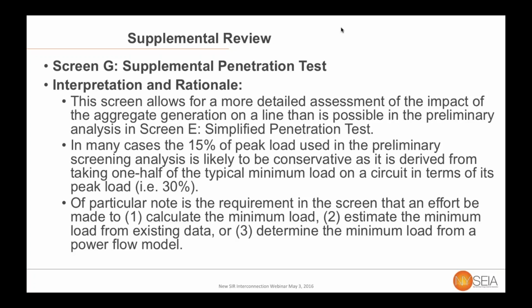It's also important to note that the screen does not require the data to exist for your particular line, but asks, can it be calculated, estimated, or determined from a power flow model? And so if the minimum load cannot be determined, if they can't make an estimate for a particular circuit, they would then explain why they weren't able to do one of these three pieces. As Melissa mentioned, the hope and the goal for all of these screens is to help increase the information flow between the developer and the utility and make sure everyone is on the same page, reducing the load on the utilities from applications that aren't likely to result in useful projects, and helping the developers interconnect more rapidly.